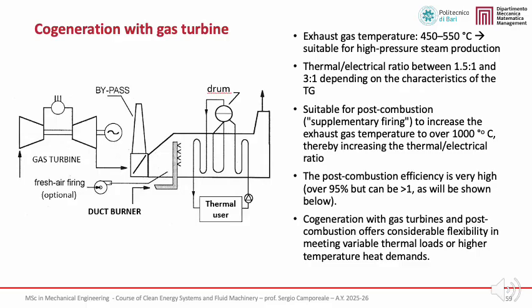At the same time, the turbine releases exhaust gases at relatively high temperatures, typically in the range of 450 to 550 degrees Celsius. These temperature levels are already sufficiently high to allow high-pressure steam production in a heat recovery steam generator. The exhaust gases are then directed to the heat recovery boiler, where thermal energy is transferred to water, producing steam or hot water for the thermal user. The presence of a steam drum indicates that this configuration is suitable for the production of saturated or superheated steam, depending on the application.